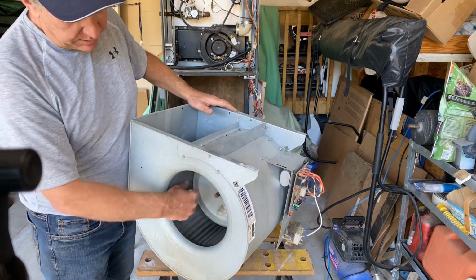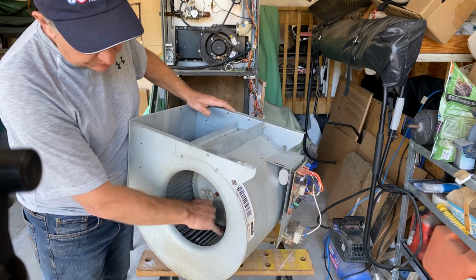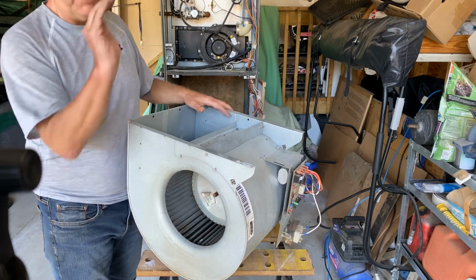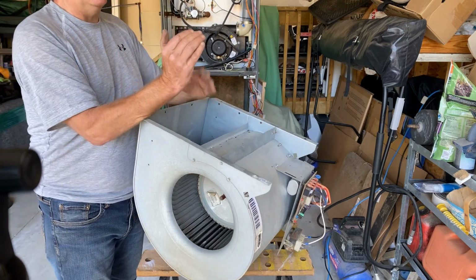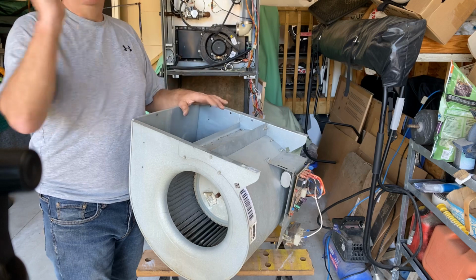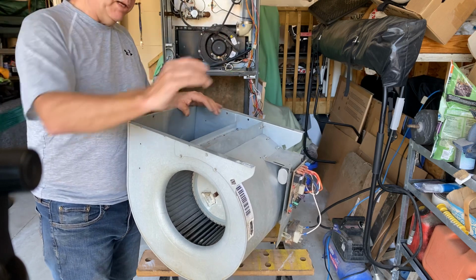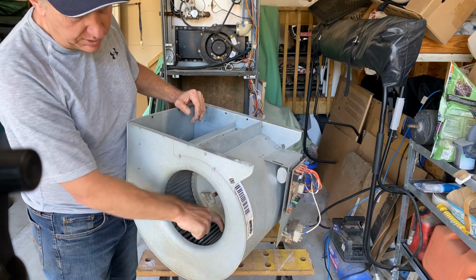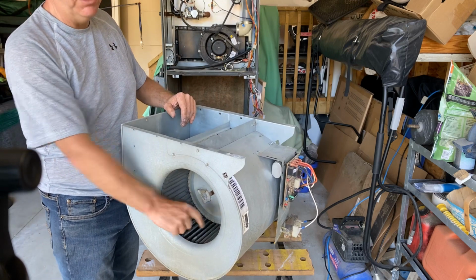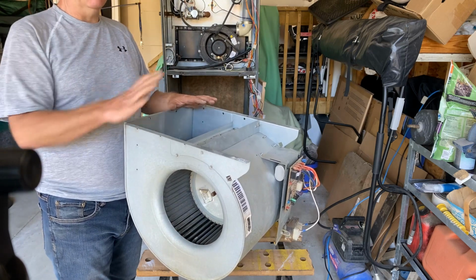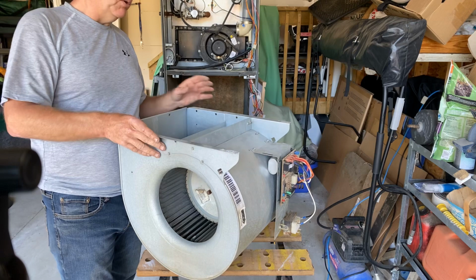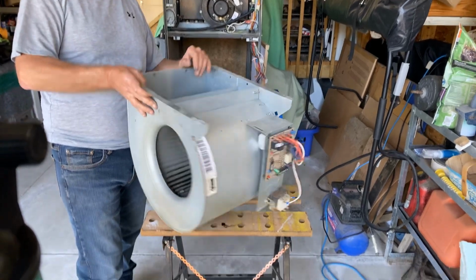While this is out, have a quick look at the fins. Remember, the fins are cupped like that. If there's any dirt in those cups, the fan won't throw the air properly. So if this blade happens to be dirty, it's a perfect time to take this outside and wash it down.